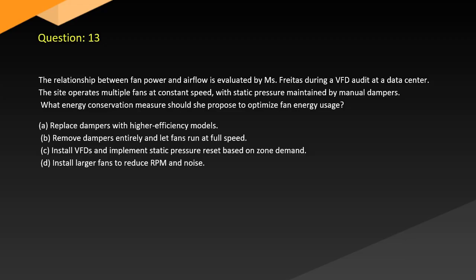A. Replace dampers with high efficiency models. B. Remove dampers entirely and let fans run at full speed. C. Install VFDs and implement static pressure reset based on zone demand. D. Install larger fans to reduce RPM and noise.